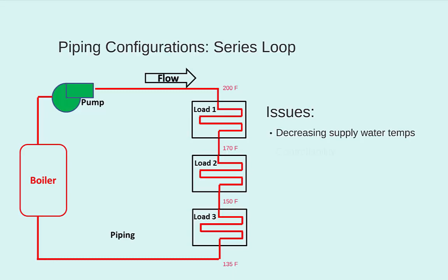The second issue is that of control. What if the space being served by the second load is getting overheated? They can't just shut off the heat being provided to them without shutting down the flow of heat to everyone else. This piping configuration is never installed anymore, but some of the older buildings on your base may still have them. One of the chapels at my first duty station had this type of piping configuration, and it created some issues for us. The only advantage to such a system is the decreased installation costs, since you get by with a lot less piping.